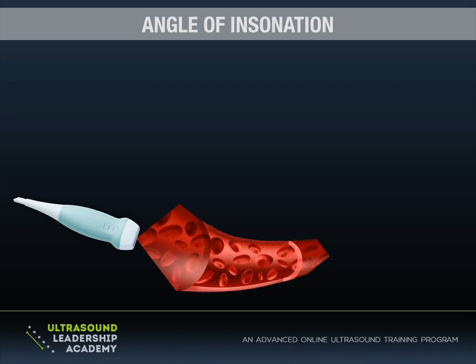Now, we can't, for all intents and purposes, place an ultrasound transducer into these blood vessels, and we can't place it at a 0 degree angle most of the time. So we have to instead deal with differing our angle to try and get the best shift that we can. So this would be an example of a positive shift where, remember, blood is flowing through this way. So it's essentially flowing towards the transducer. Now, this is the angle of insonation here, that angle. And you don't have to worry about figuring that out.